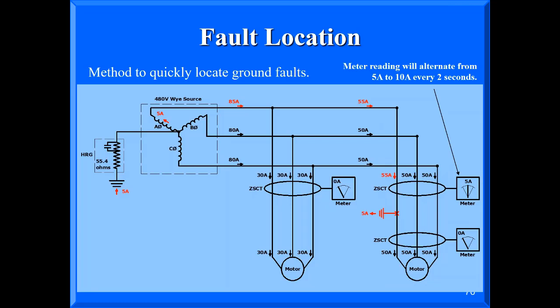Okay? First set, I got nothing. Second set, I went around, and I'm seeing it still pegging. So then I isolated which conduit it was. Because it was an MCC, we could open up the trough, and I found out which circuit it was. Turned out, long story short, it was a space heater and a motor that was going to ground. So you literally can find the fault on these high resistance grounding systems.